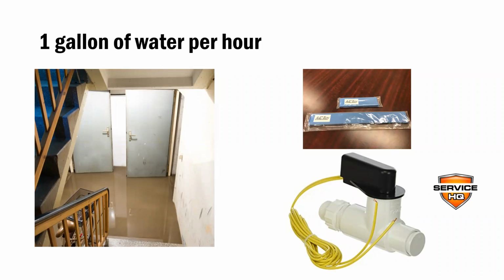You've got a cold evaporator coil, and you've got hot, humid air being passed over that coil, and any moisture in that air condenses onto the coil and needs to drain somewhere. And on really hot, muggy days, it can be a gallon of water per hour that's draining out of your system. So you don't want to have to walk down in your basement and see this, which could happen if it was left undetected for any amount of time.